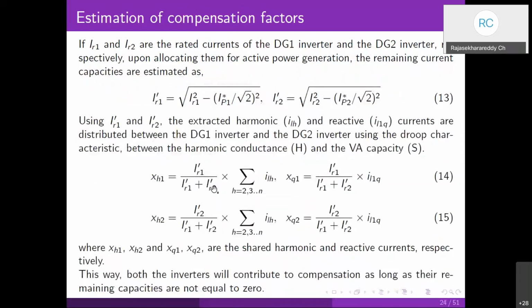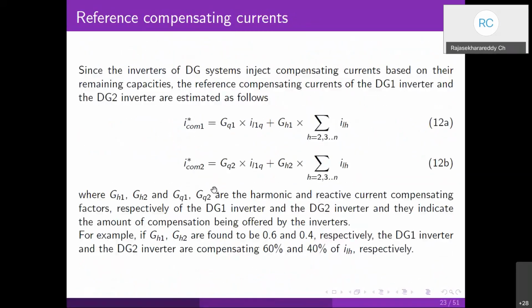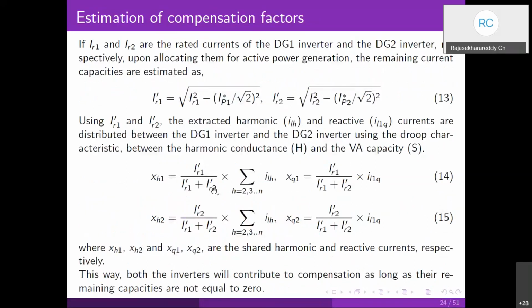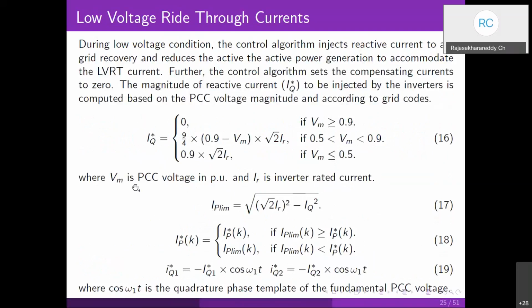Once we have XH1, XH2, XQ1 and XQ2, we compensate with these compensation factors instead of using ILH and IL1Q. Once we have these compensation factors, we need to calculate the low voltage ride through current. During low voltage conditions, the control algorithm injects reactive current to aid the grid recovery and reduces the active power generation to accommodate the LVRT current.